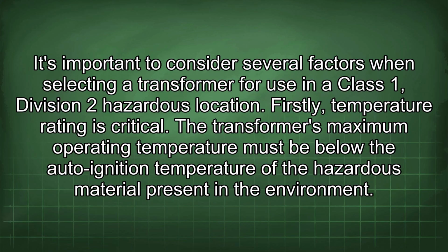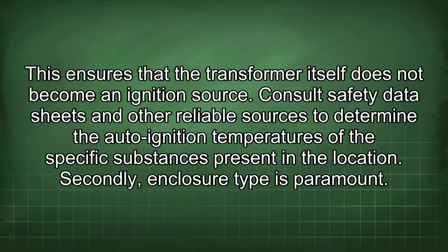It's important to consider several factors when selecting a transformer for use in a Class 1 Division 2 hazardous location. Firstly, temperature rating is critical. The transformer's maximum operating temperature must be below the auto-ignition temperature of the hazardous material present in the environment. This ensures that the transformer itself does not become an ignition source. Consult safety data sheets and other reliable sources to determine the auto-ignition temperatures of the specific substances present in the location.